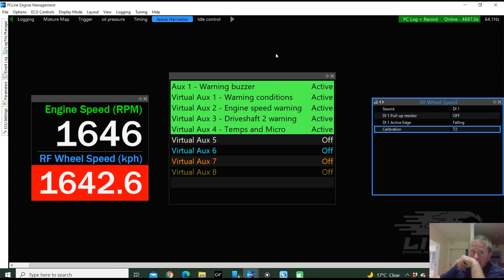Then we're going to bring it up to 1900, so the drive shaft warning and the engine speed warning should no longer be active — they should be inactive, but the temps and micro should remain active because that microswitch is presently open circuit. So here we go — a warning buzzer is still going off because the microswitch is tripped.